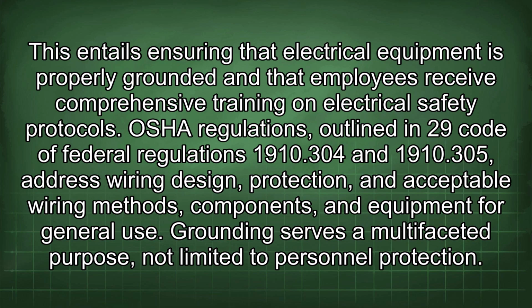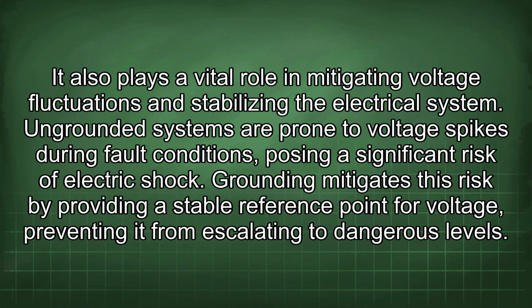Grounding serves a multifaceted purpose, not limited to personnel protection. It also plays a vital role in mitigating voltage fluctuations and stabilizing the electrical system. Ungrounded systems are prone to voltage spikes during fault conditions, posing a significant risk of electric shock. Grounding mitigates this risk by providing a stable reference point for voltage, preventing it from escalating to dangerous levels.